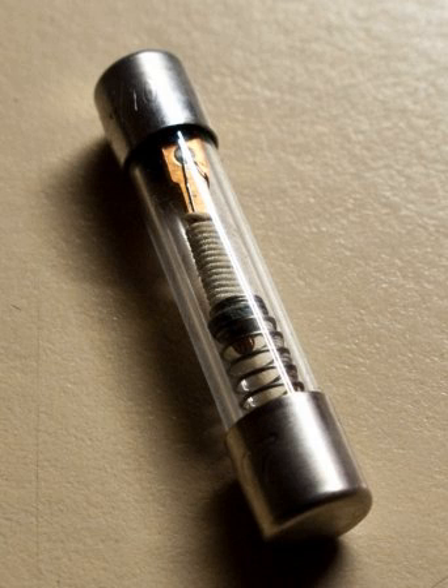The hot gases are then explosively expelled out of the ends of the fuse. Such fuses can only be used outdoors. These types of fuses may have an impact pin to operate a switch mechanism, so that all three phases are interrupted if any one fuse blows. High power fuse means that these fuses can interrupt several kiloamperes. Some manufacturers have tested their fuses for up to 63 kiloamperes short circuit current.